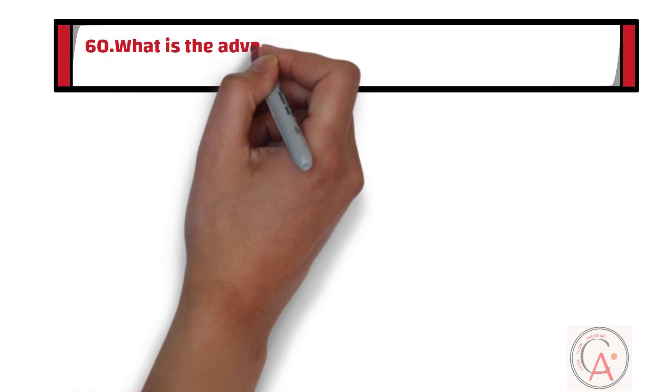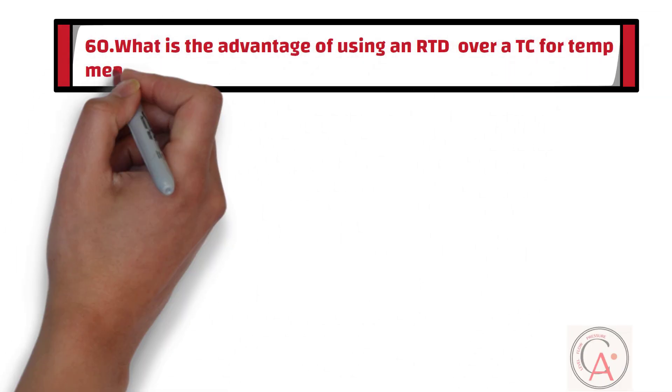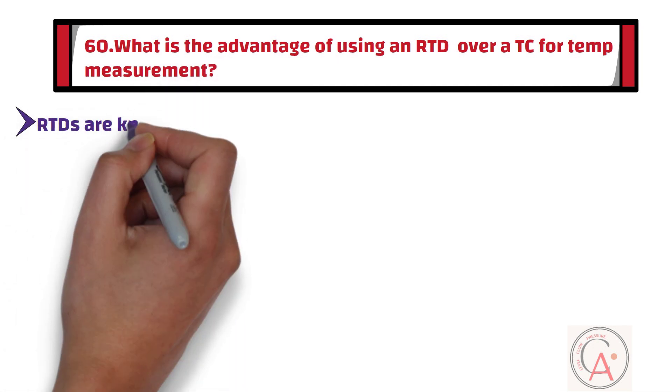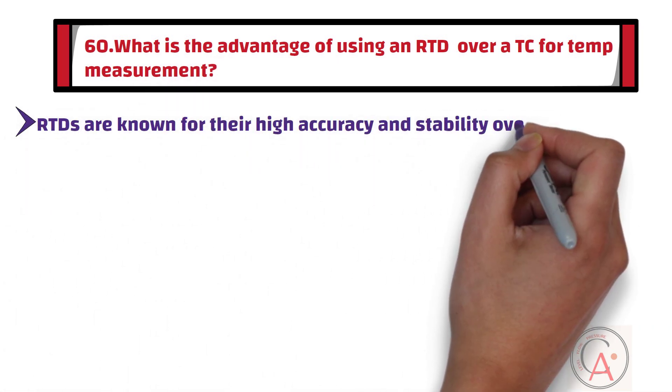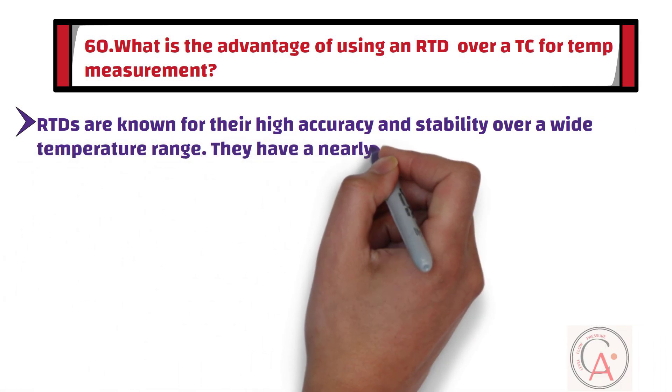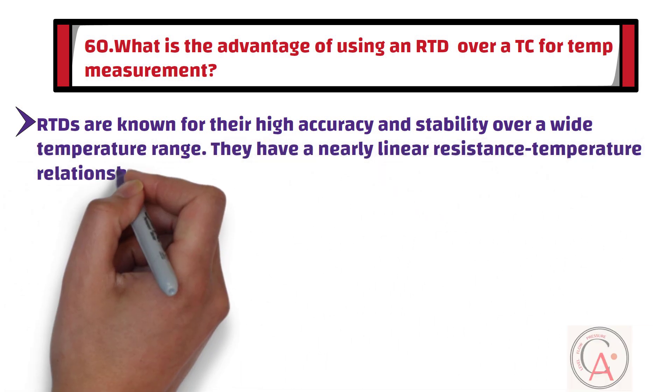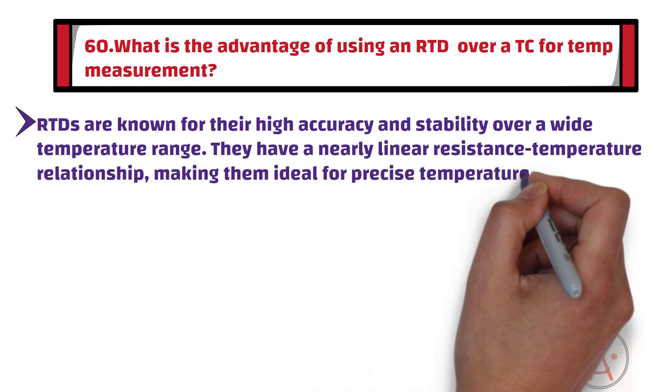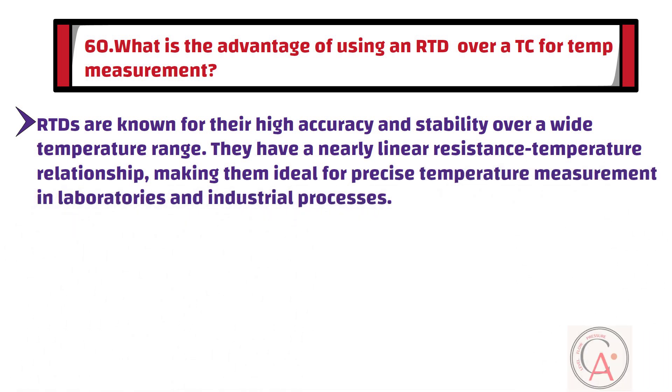Question number 60: What is the advantage of using an RTD over a thermocouple for temperature measurement? RTDs are known for their high accuracy and stability over a wide temperature range. They have a nearly linear resistance temperature relationship, making them ideal for precise temperature measurement in laboratories and industrial processes.